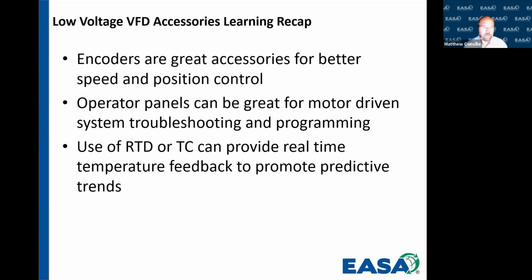So let's kind of recap things, and then we're going to open it up for questions. We learned today that encoders are great accessories that are going to give us better speed and position control. Operator panels, whether they be basic or advanced, are going to be great for motor-driven systems for troubleshooting and programming. If we use an RTD or a thermocouple or even a thermistor, we can provide real-time temperature feedback, and we can promote predictive trends so that we can actually prevent or understand whenever we have a step change that might cause a failure in the future.